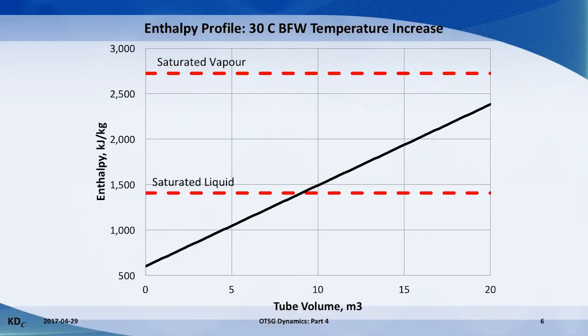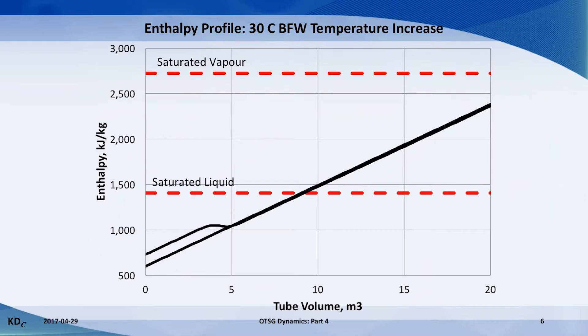We will start with boiler feed water at 150 degrees, making 74% quality steam. Then we will increase the water temperature by 30 degrees to see what happens in the OTSG. We will note that the liquid volume in the OTSG currently is 9 cubic metres. The hot front slowly moves through the convection section, changing from a harsh step to a more gradual smear. This is due to the thermal mass of the steel in the OTSG piping.